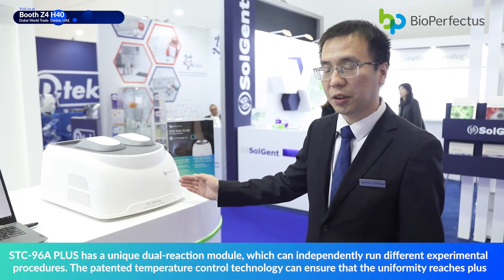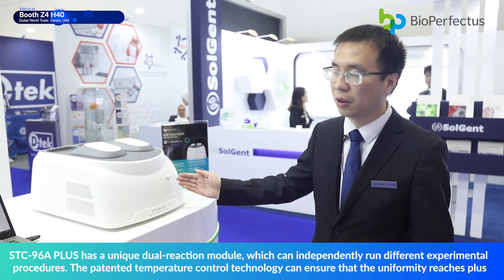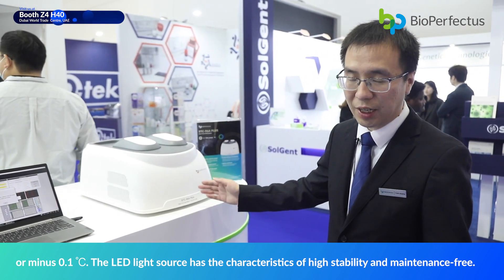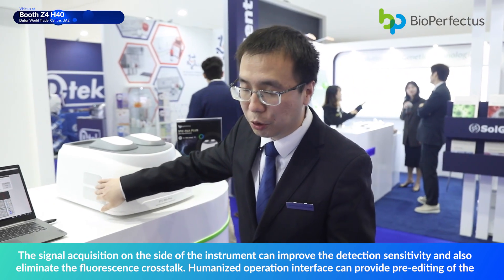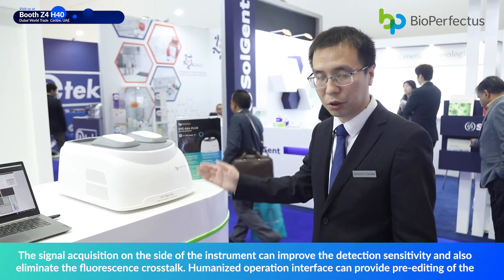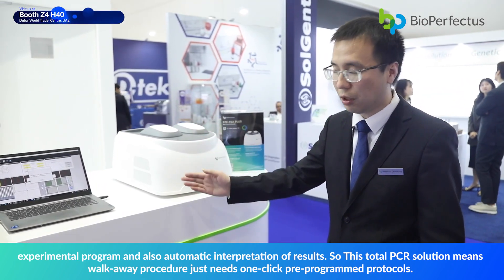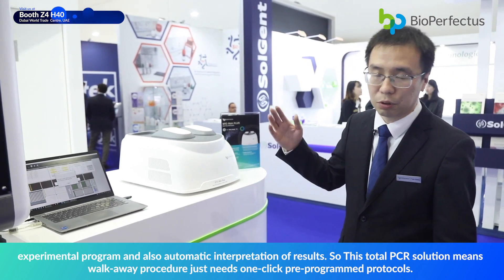STC-96A Plus has a unique dual reaction module which can independently run two different experimental procedures. The precise temperature control technology ensures uniformity reaches plus or minus 0.1 degrees. The LED light source has characteristics of high stability and is maintenance-free. Signal acquisition on the side of the instrument improves detection sensitivity and eliminates fluorescence crosstalk. The humanized operation interface provides pre-editing of experimental programs and automatic interpretation of results — making this a total PCR solution with a walk-away procedure requiring just one-click pre-programmed protocols.